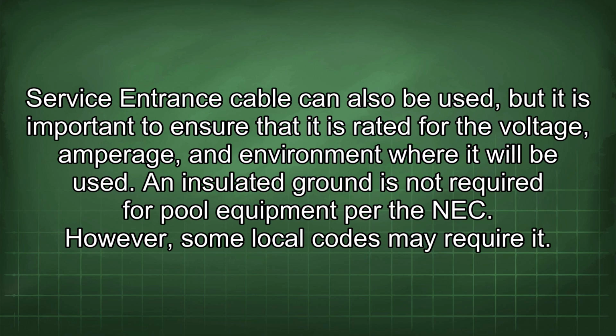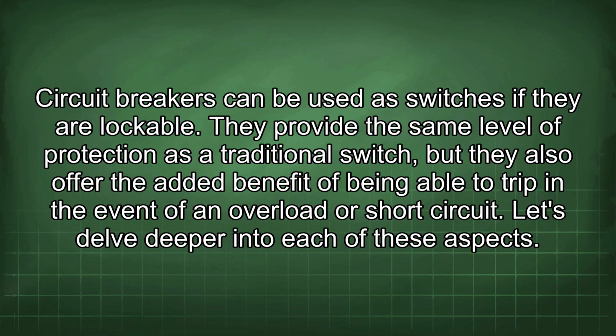An insulated ground is not required for pool equipment per the NEC. However, some local codes may require it. Circuit breakers can be used as switches if they are lockable. They provide the same level of protection as a traditional switch, but they also offer the added benefit of being able to trip in the event of an overload or short circuit. Let's delve deeper into each of these aspects.